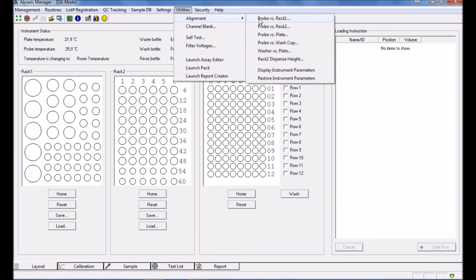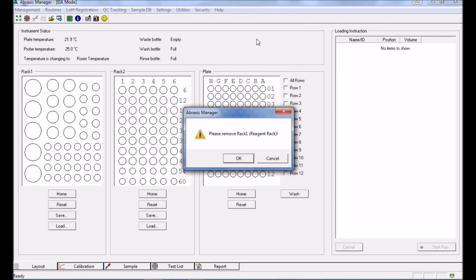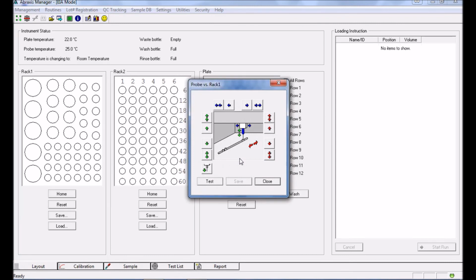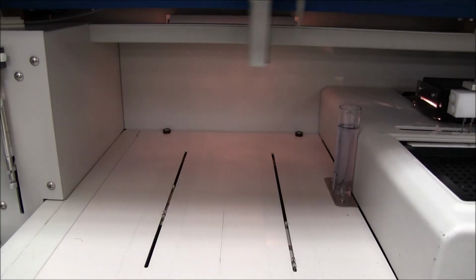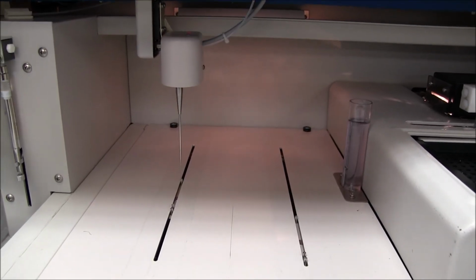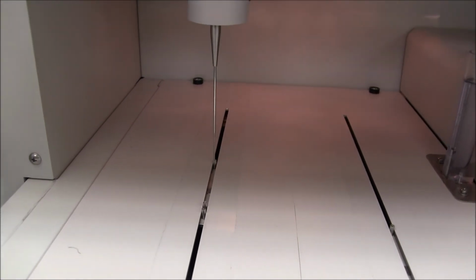At the top middle of the screen, click on Utilities, then Alignment, then choose Probe versus Rack 1 and click OK. Click the Test button to see how the probe is currently aligned over the pin. When the probe is aligned properly, it should hover a few millimeters above the pin, but it should never be touching the pin.